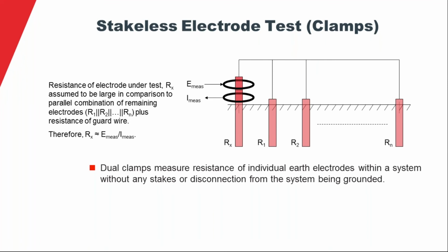Okay, and then we have Clamp-On, and in this method, you have Clamp-On ground testers that actually have two windings in the jaws. They look like a clamp-on ammeter, but actually they have two windings, both current and voltage. And so you clamp over your ground rod, and what happens is it inductively establishes a test current on your ground rod that will travel through the soil, and it will seek out its own return, which usually will be the grounded utility. So it's working similar to the dead earth method does, except that the utility is generally grounded at a very small number, and so it's contributing a lot less. Still reads a little bit high, but generally not by very much. So where it's applicable, the Clamp-On method is really good to use. It's quick. You're out of there in a hurry.